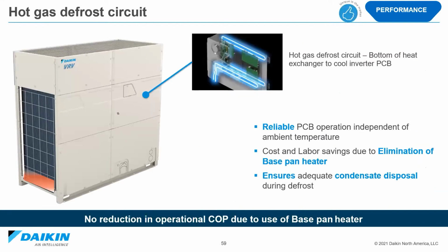The coil design has a separate hot gas defrost bottom circuit that allows for installation without a base pan heater. So it's reducing costs there. The inverter PCB is now refrigerant cooled by the circuit, which balances the inverter temperature independent of ambient temperature outside. And during heating mode, it reduces ice buildup. So the bottom 7 or 8 inches of this coil will always be in heating because it's cooling the inverter. And thus, during wintertime, it's going to be pre-defrosting, even when the coil circuits above it are building up ice. And this is going to reduce defrost time.